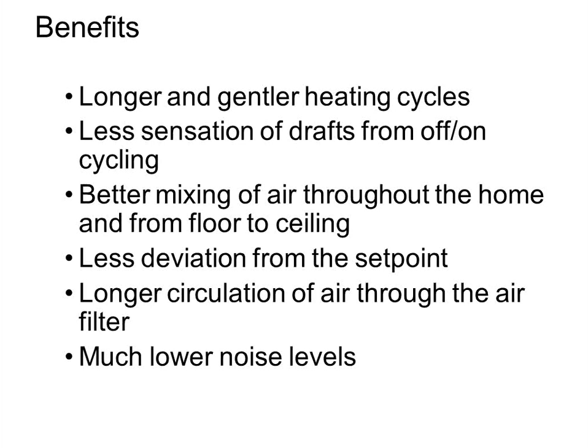This furnace shuts off, the ductwork gets cold because it's bordering the attic or bordering the garage attic, and then you first turn the furnace on, and then that cold duct has to warm up again before it goes into the bonus room. Well, if the duct's always got heat in it and it's always warm, I don't have that differential, and hence I don't have to overcome it, and hence I can have more heat actually go into the bonus room.